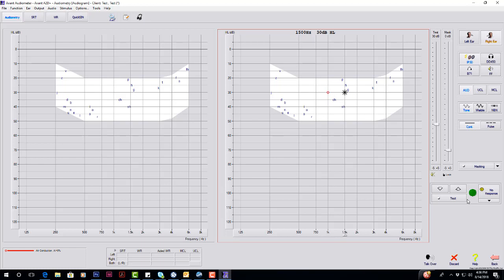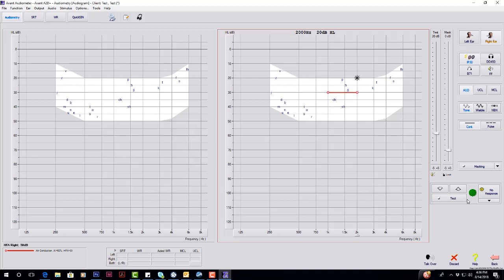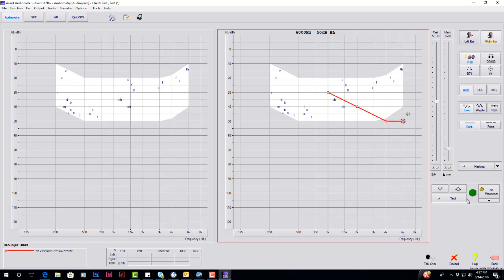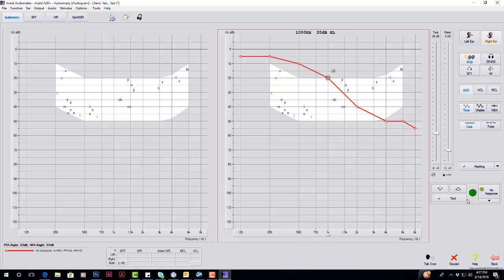Once you've determined the frequency and hearing level you want to keep your point at, just hit the right or left arrow keys to change frequency. I'm going to put in an audiogram here real quick. There's no savings, so you can always go back and retest. We always retest 1000, and then you're all set for air conduction on the right ear.